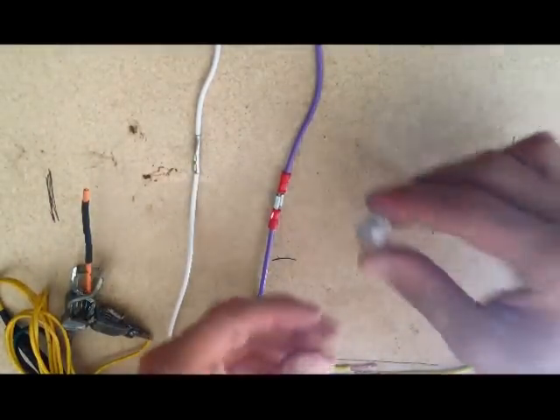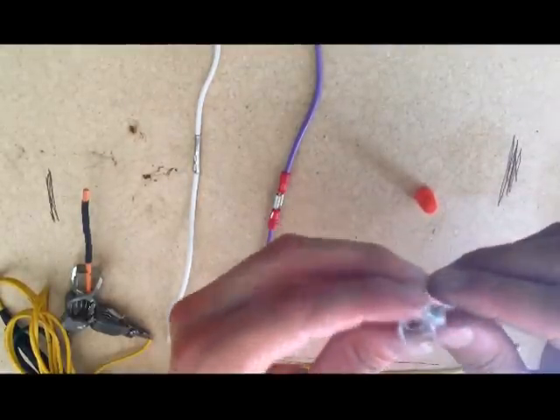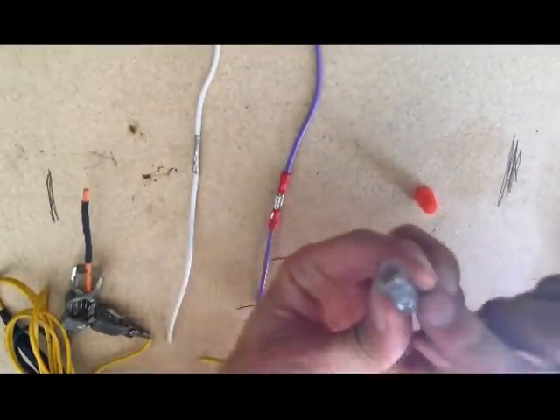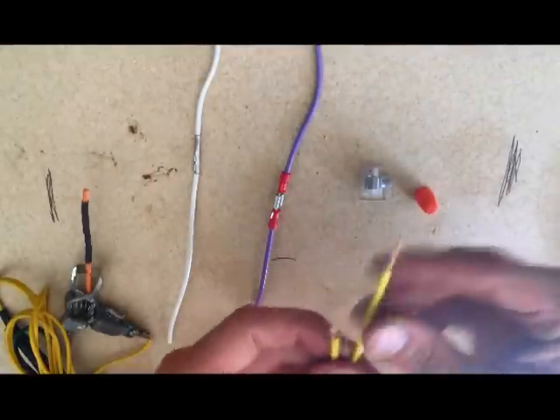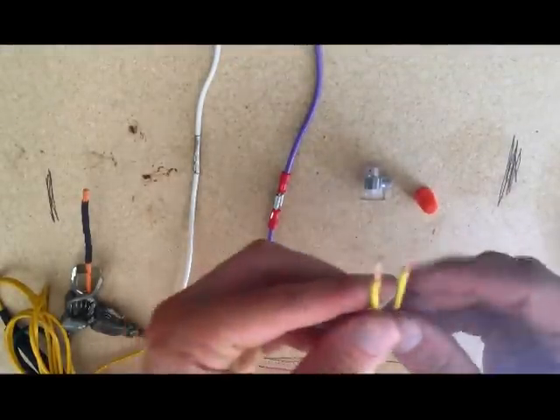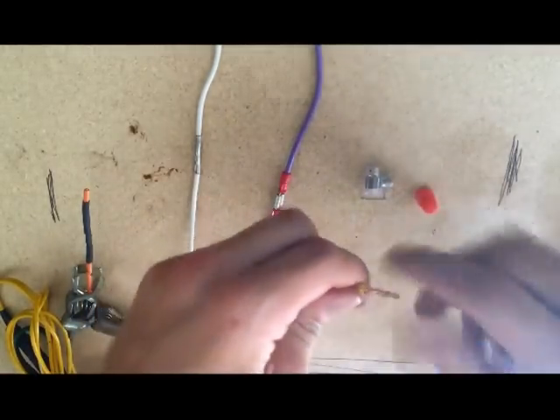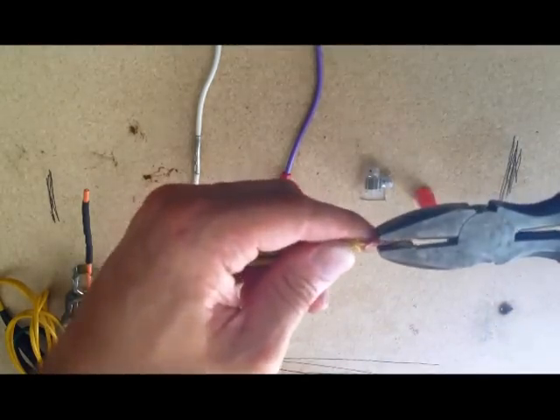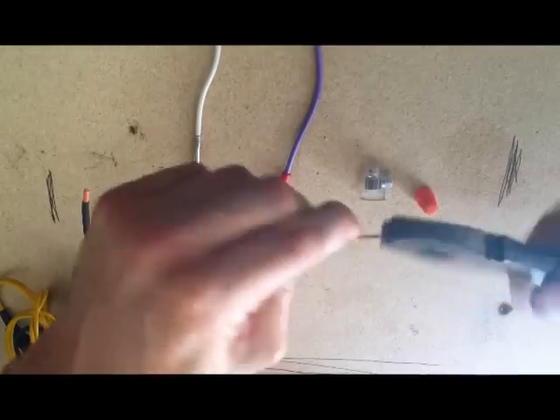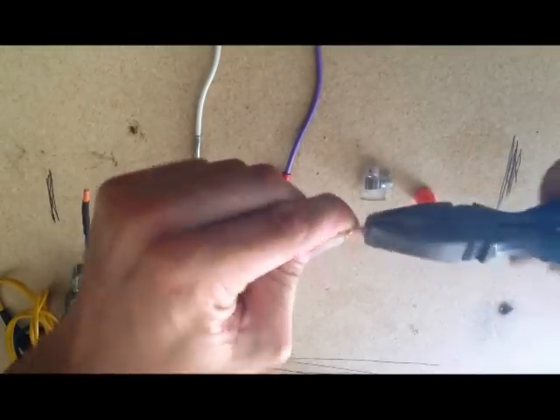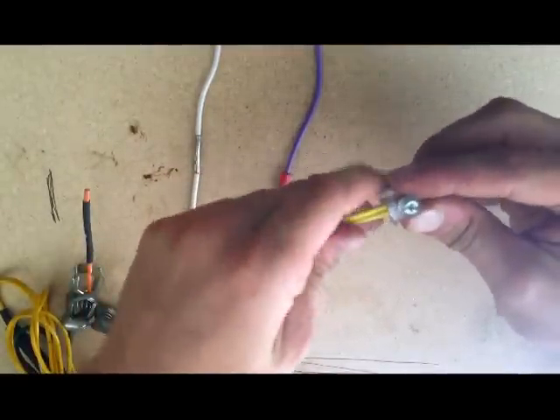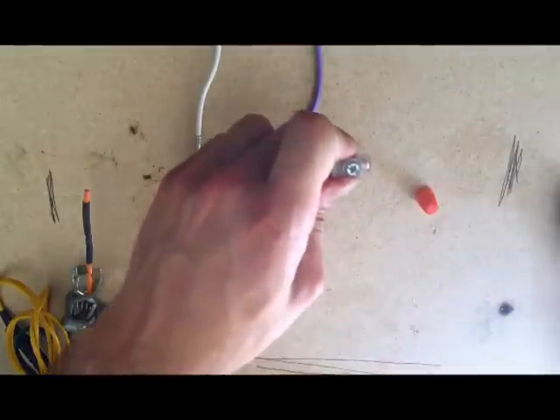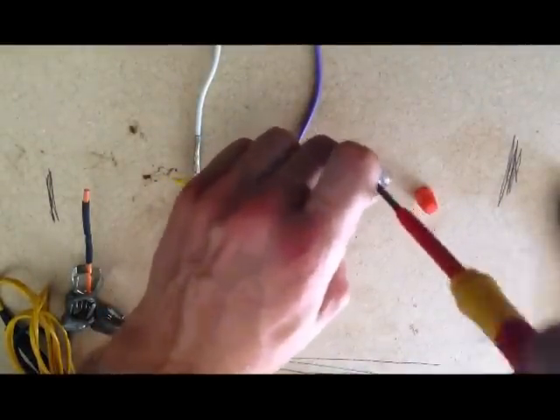Okay the next terminal we're going to use is just this little clear clamp down terminal. It's got a little copper inner inside of it and a screw that clamps down on top of the wires. Okay so the best way to do that is to grab your two bits of wire and strip them a good half inch back. Basically twist them together by hand. Like so. And then I like to grab a pair of bullnose pliers and twist them up just sort of gently with the bullnose pliers. So that they're nice and snug together. Nice tight twist. And then they can slide into the terminal until the insulation is well in there. And then get a screwdriver and screw that down on top. Clamp it in nice and firm.